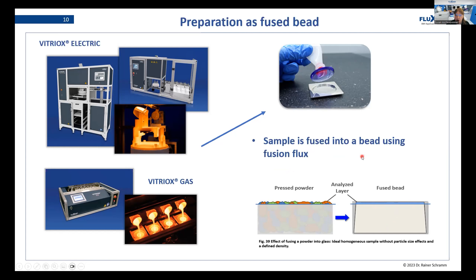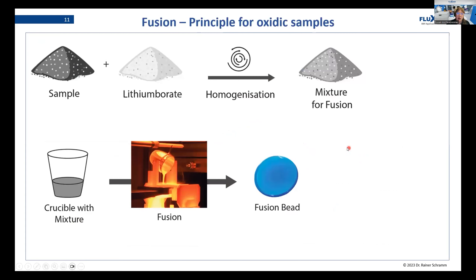Another advantage of preparing as a fused bead is that you don't have any particle size effects. This is because the fused bead is completely homogenized and your analyzed layer will always be a perfect representation of your whole sample. In general, the sample is fused into a bead using fusion flux.